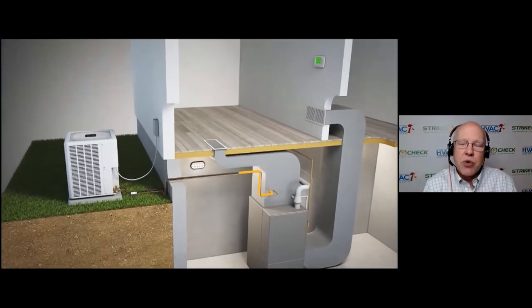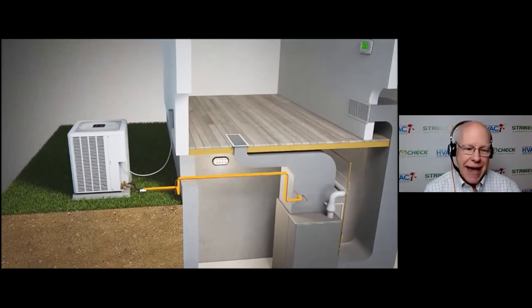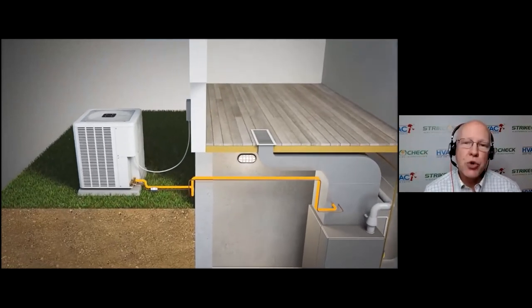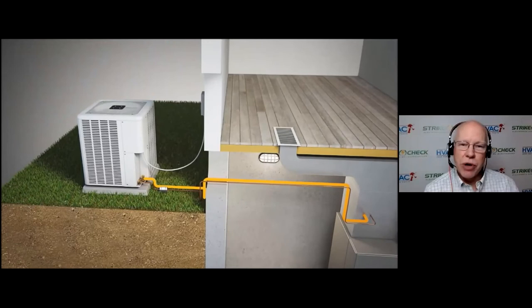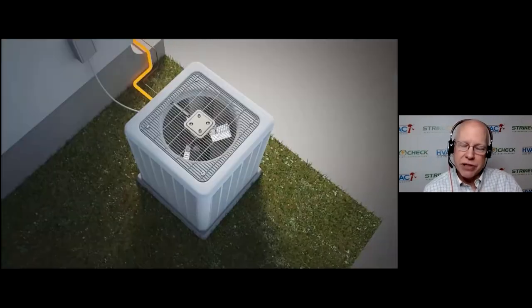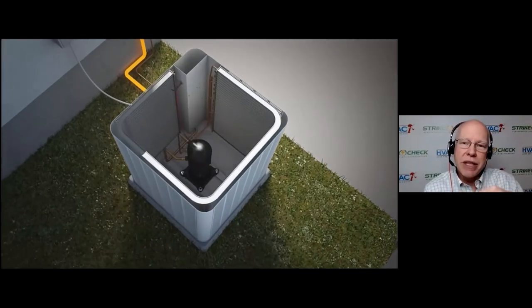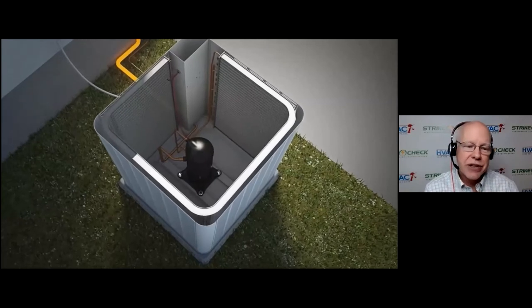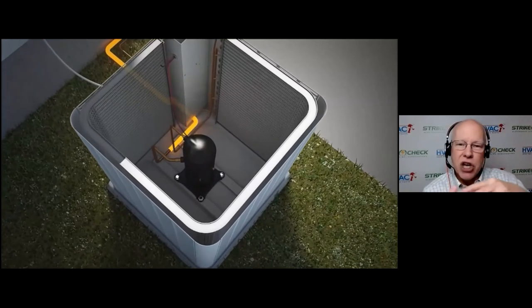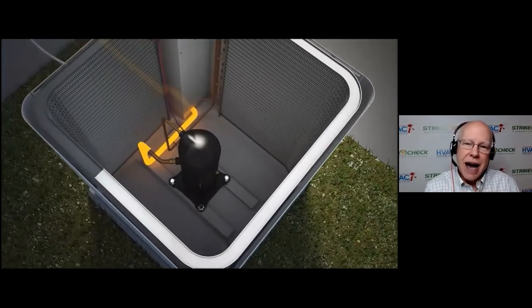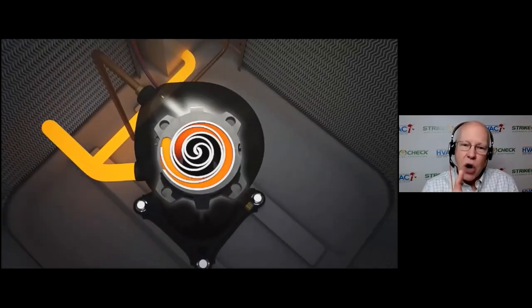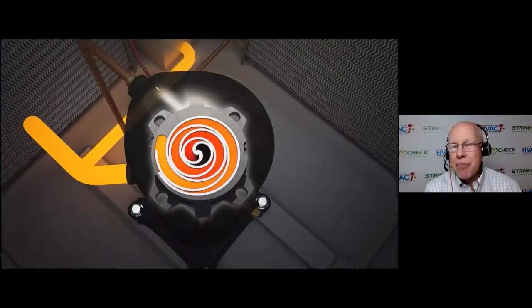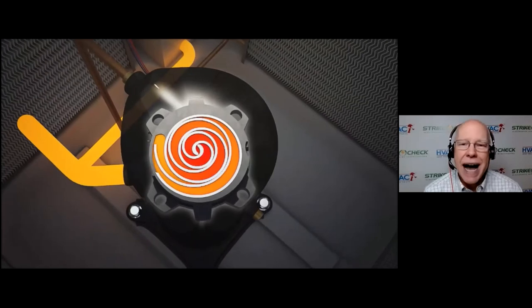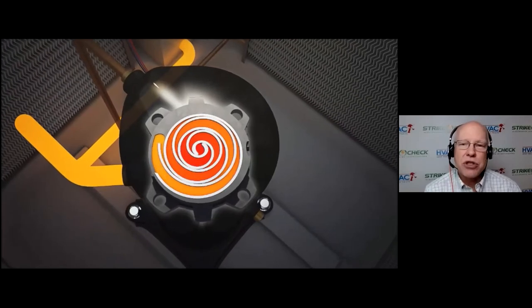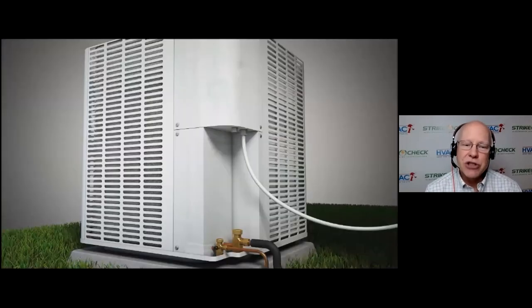The system starts running. It starts pumping that gas refrigerant to the compressor. And this compressor is called a scroll compressor. And you'll see as we open it up, these two scrolls are going against each other. And this gas refrigerant, as it's going through the scrolls, is getting hotter and hotter and hotter, and the pressure is going up. By the time it comes out of the top port of that scroll compressor, it's a hot gas refrigerant going out to the condenser coils.